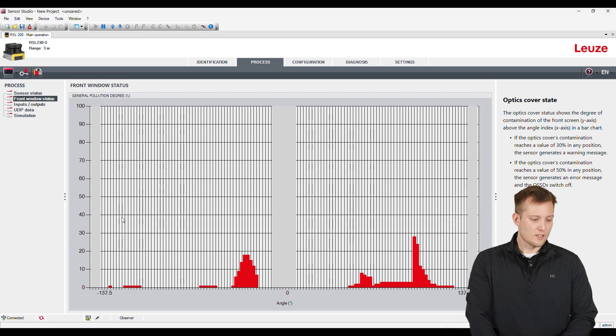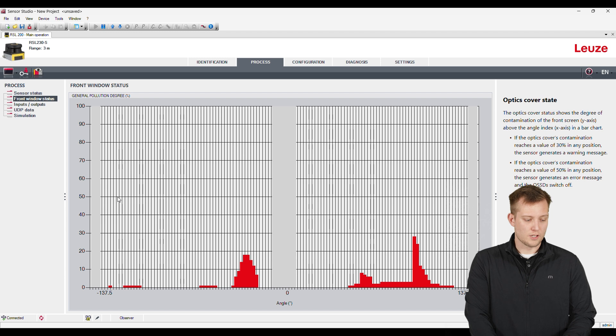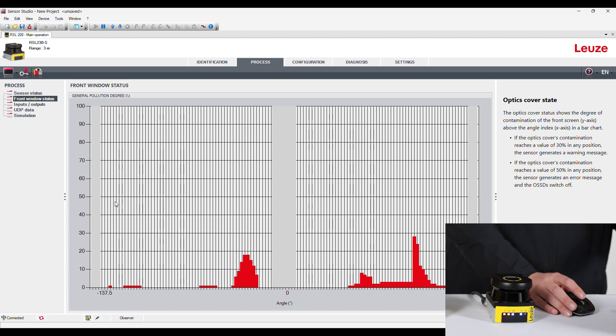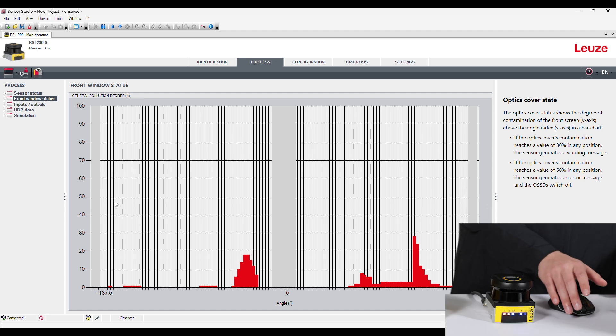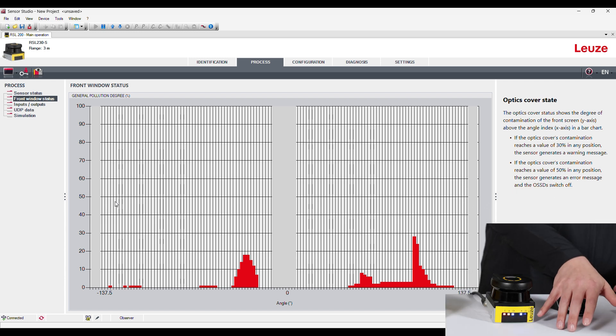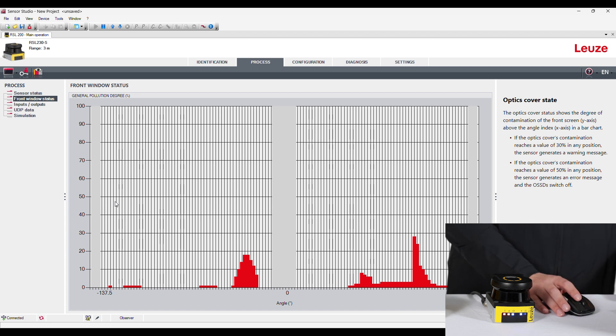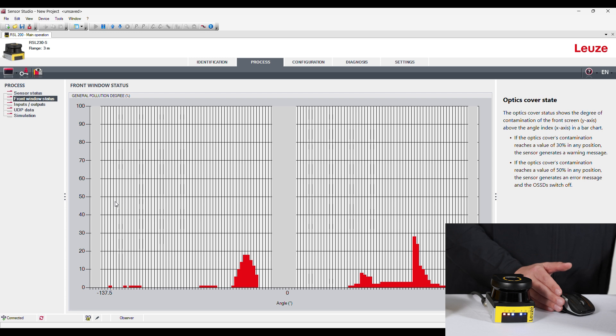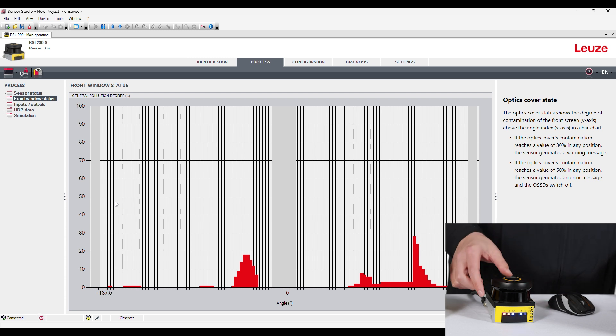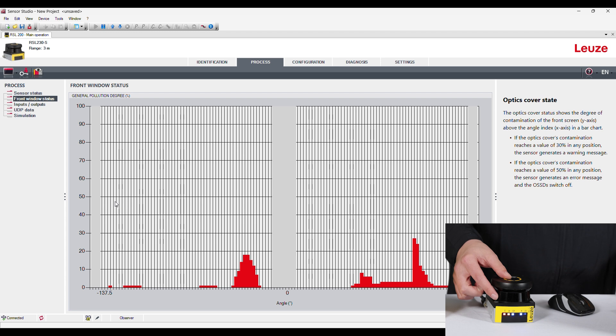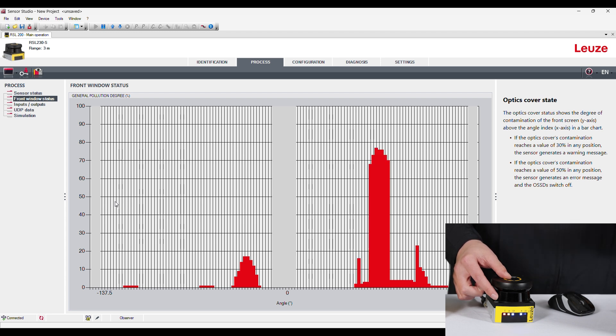They're measuring this in general pollution degree. So if this gets above 30%, there's a small LED on the front of this sensor here, and that will turn solid, letting us know that it needs to be cleaned. So if I put my finger here on the lens, you're going to see right where my finger is, and it's going to go up now above.